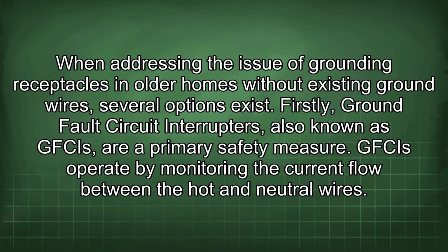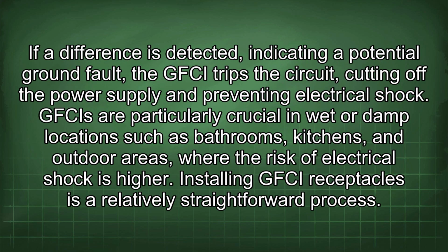When addressing the issue of grounding receptacles in older homes without existing ground wires, several options exist. Firstly, ground fault circuit interrupters, also known as GFCIs, are a primary safety measure. GFCIs operate by monitoring the current flow between the hot and neutral wires. If a difference is detected, indicating a potential ground fault, the GFCI trips the circuit, cutting off the power supply and preventing electrical shock. GFCIs are particularly crucial in wet or damp locations such as bathrooms, kitchens, and outdoor areas, where the risk of electrical shock is higher.